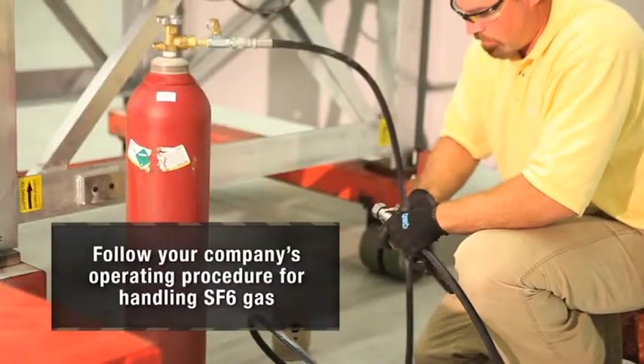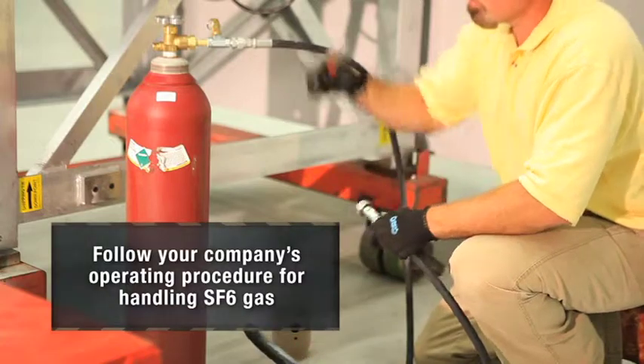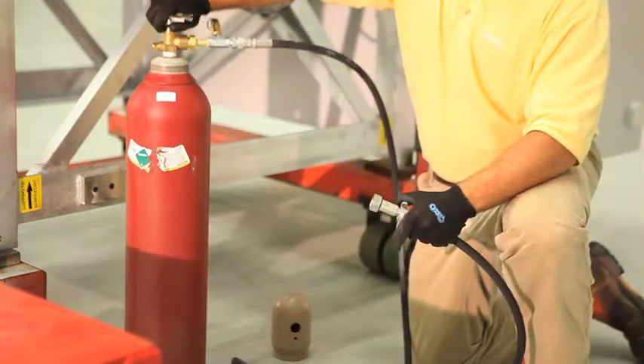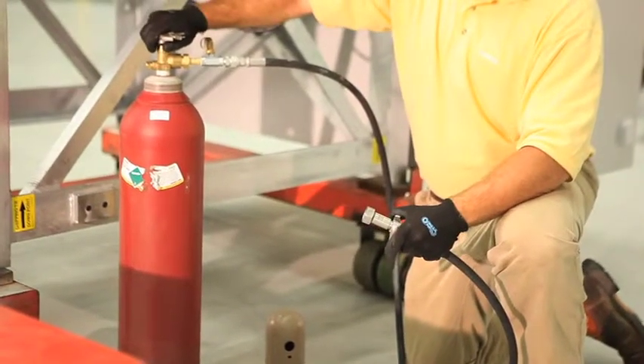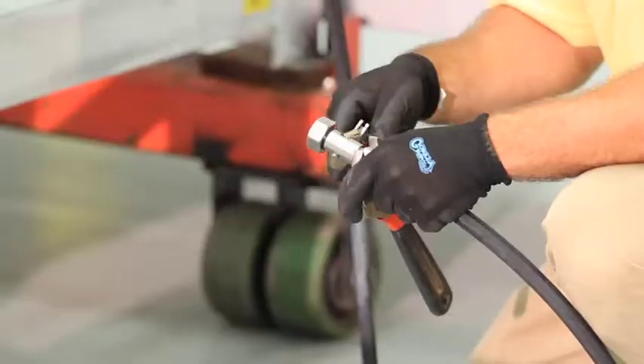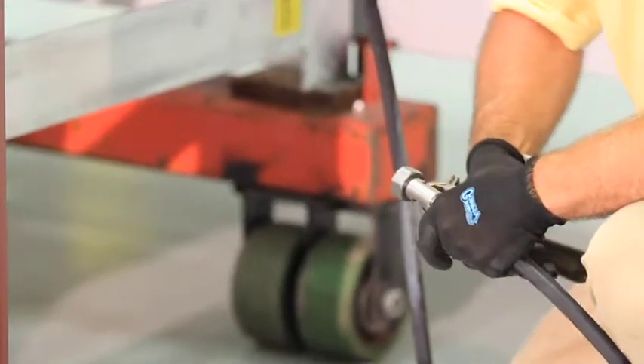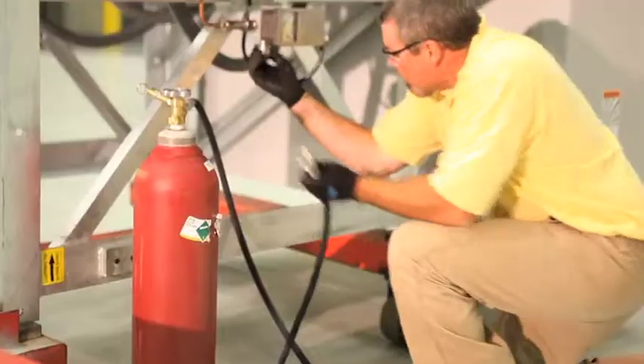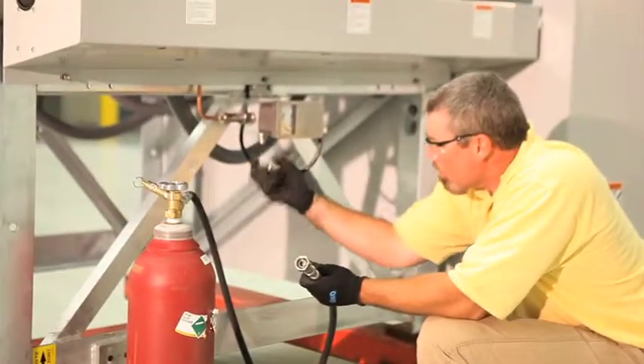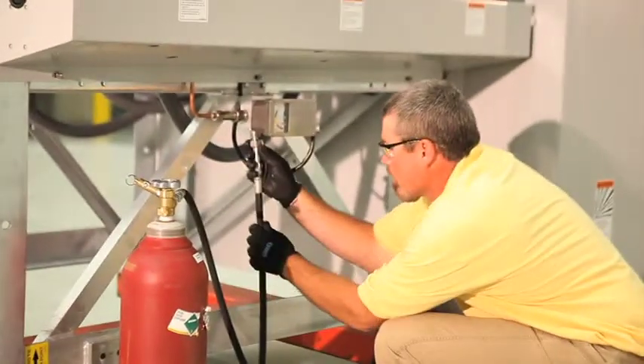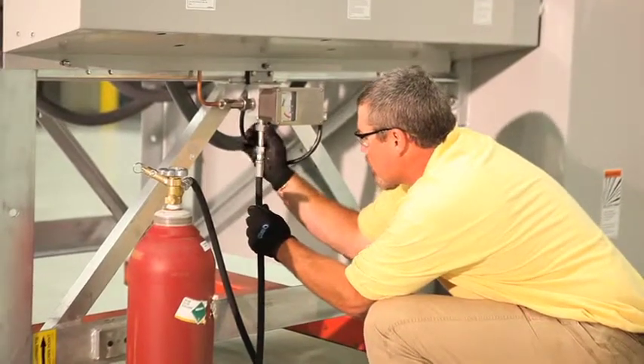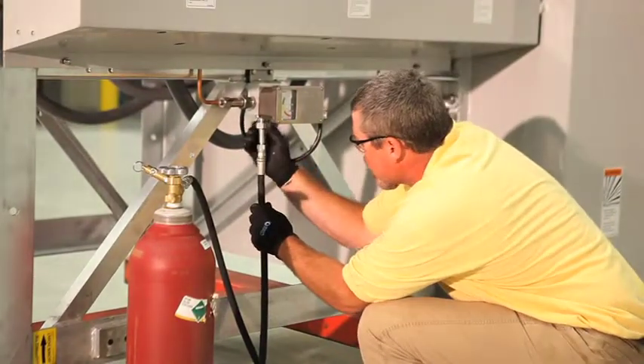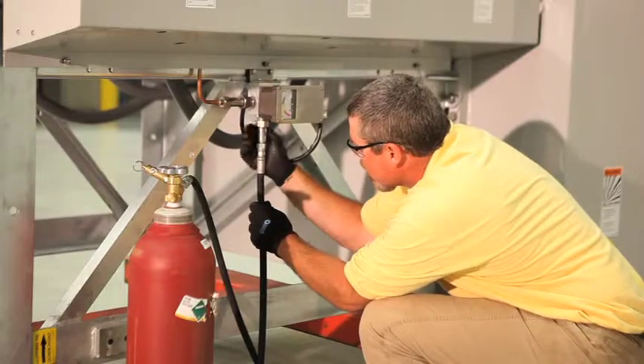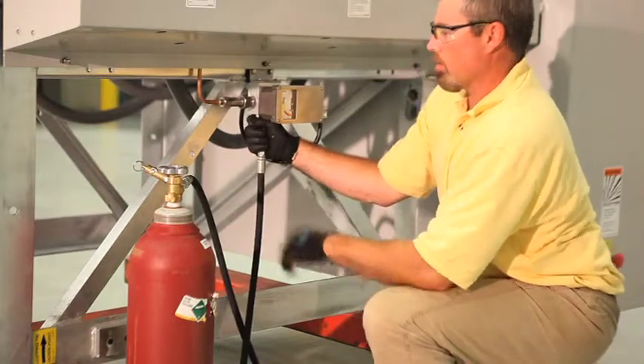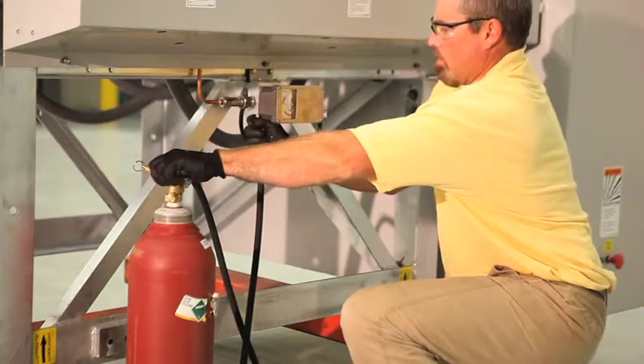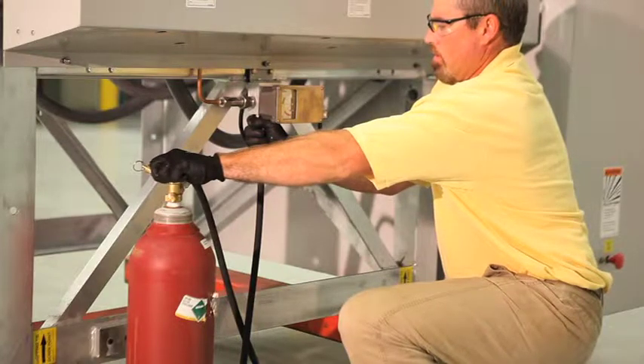Loosen the disconnect fitting, then crack the SF6 cylinder valve, allowing SF6 to flow out the loosened fitting long enough to purge air from the hose. Close the valve and tighten the quick disconnect fitting. Connect the hose quick disconnect fitting to the breaker. The circuit breaker service connection and the hose quick disconnect are matching fittings which are both sealed when disconnected. When connected together, the seals are opened, allowing gas to flow. Open the SF6 cylinder valve, slowly transfer SF6 into the breaker.